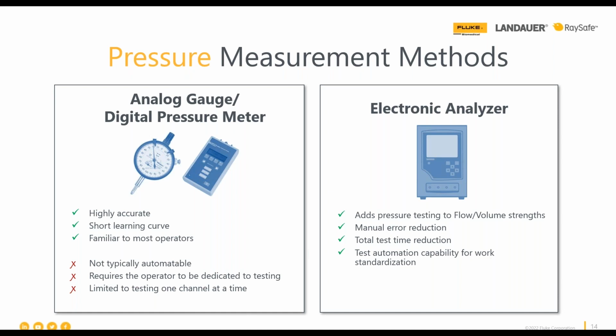So if you're reading for an occlusion, you have to be watching that meter when your pump hits max pressure and starts to back down off. Another question there is if you want to measure that residual flow after it backs off the pressure, you can't really do that with a pressure gauge. So there's some challenges there as well. Electronic analyzers, again, we can streamline some things, reduce the error, reduce the setup time in between testing, and you can go ahead and maybe even automate your work with some of the analyzers out there. So those are some of the current test methods that we have.